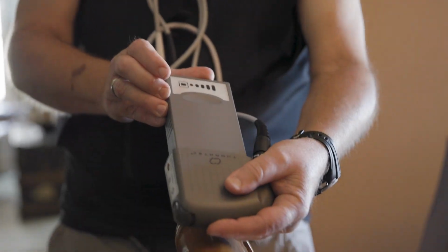Right. So spontaneous failure of the pump outside of just battery draining is very, very rare. If you encountered a patient whose pump was not working, first thing you would want to check is power and all of your connections, right? Are we connected to an adequate power source? And is their drive line connected to that controller? If those things are working and you still don't have your pump turning on, ideally you could have someone else troubleshooting while someone else was supporting the patient, right? So fluids, pressors, all ACLS medications. Caregivers are very extensively trained generally before they go home with the LVAD. They can teach you how to change out a controller, to switch to their backup controller. And we would try everything to get the pump working before we would jump to CPR, but CPR can be used as a last resort.